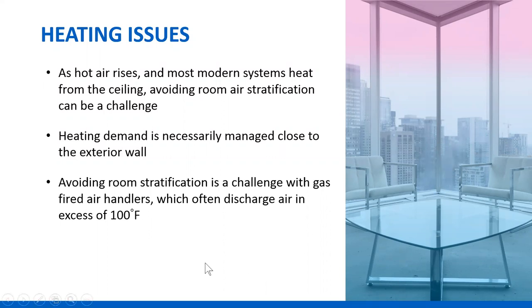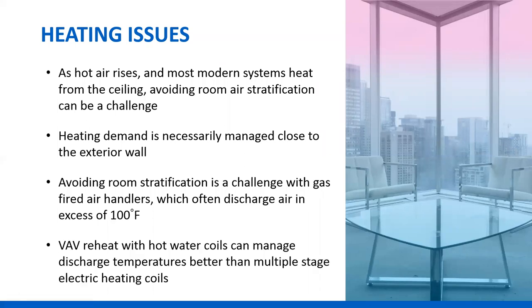We're seeing proportional gas valves on gas-fired rooftops, which allow you to go to lower flows. With a hot water coil on a VAV reheat box or a fan coil, we can have infinite control of discharge temperatures much better. Electric heat with its stages often finds that the first stage is not enough and the second stage is too much, resulting in the room getting stratified. We've actually recommended people disconnect the second and third stages of electric heat when rooms are terribly stratified.